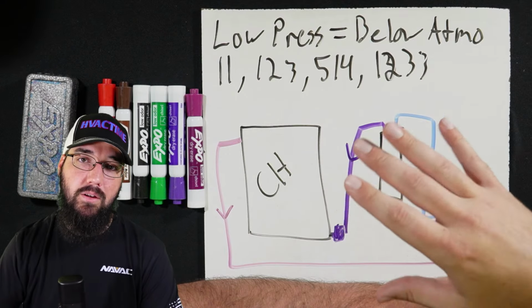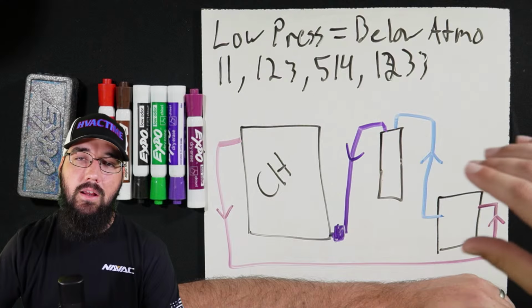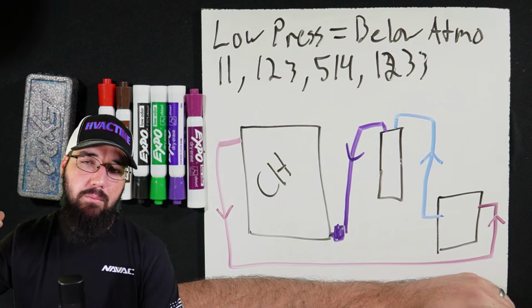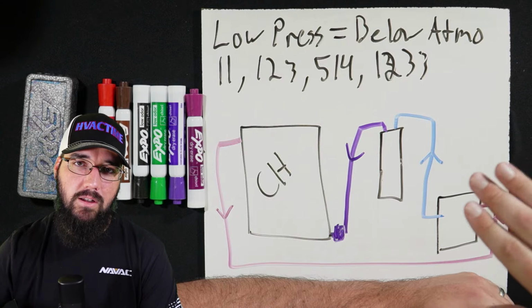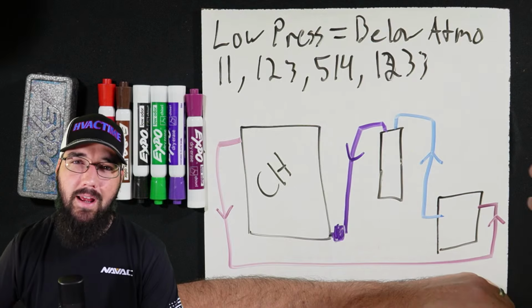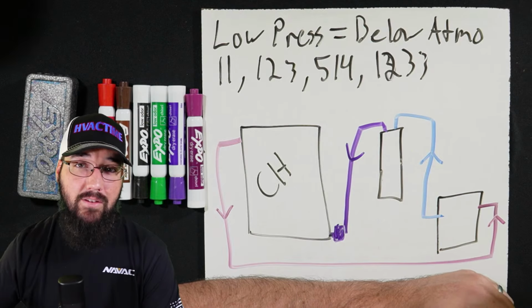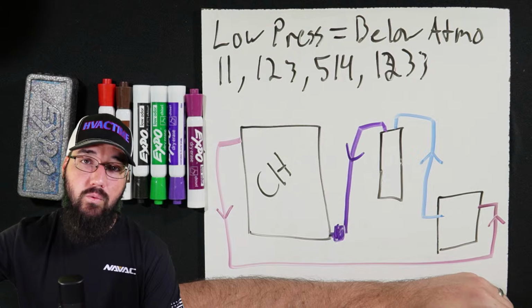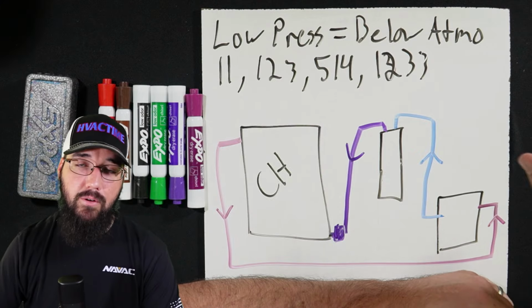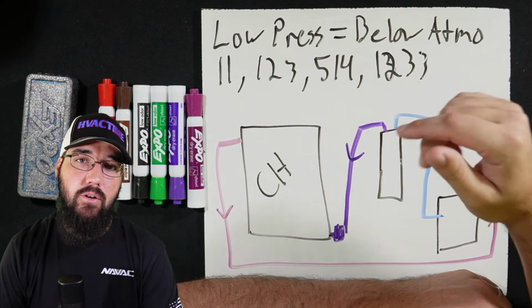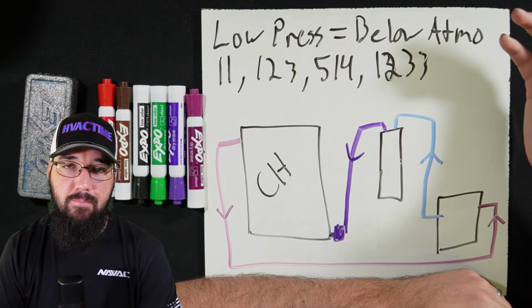and then hold that cylinder up above the evaporator. And you don't have to go literally above, just above where the liquid level line is for the evap, which is about halfway. As long as you're above that, that liquid refrigerant will drain. It won't do anything for your vapor, but it will drain that liquid charge into the machine.